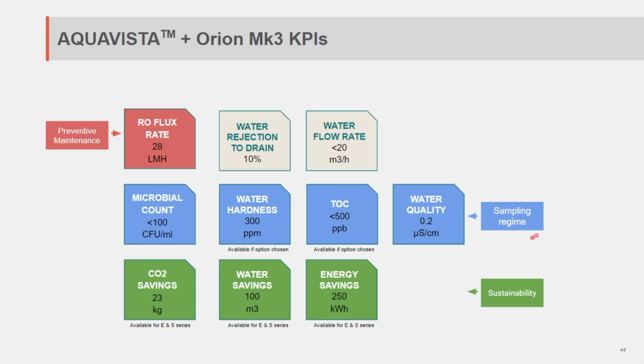And the RO flux is probably one of the biggest things you have to worry about on an RO CDI system. Other things you can measure are things like water rejection to drain. Make sure the flow rate is what you require. So if it's a 4 meter cubed an hour system, you're producing 4 meter cubed an hour consistently. Also, the quality of water, so the sampling regime, can be trended on the system. So water quality in terms of conductivity. If you have a TOC monitor, the TOC can also be trended within this system. And if you have a hardness monitor as an option, that can also be trended on this system.